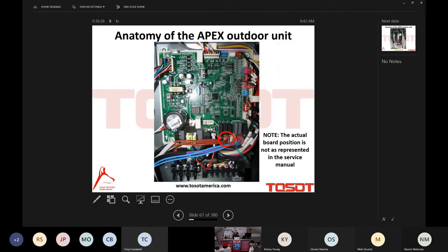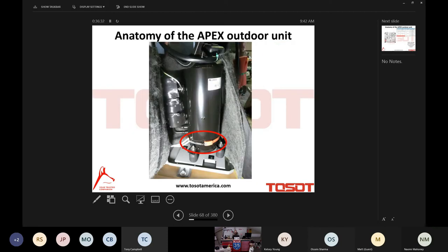There's also a heating element for the compressor itself. You can see that heating element there. I've circled it for you. At the base of the unit, it's literally strapped around the compressor. Guys, here's note number 4 or 5, whatever we're up to. That compressor needs to be preheated before the system operates for the first time. Now, what does that mean? It's pretty serious stuff. Tosot wants that unit to be energized, not turned on. We don't want an active call for cooling or heating. We just want the outdoor unit to be powered. Listen to me now, for a minimum of 8 hours before the system is operated for the first time.